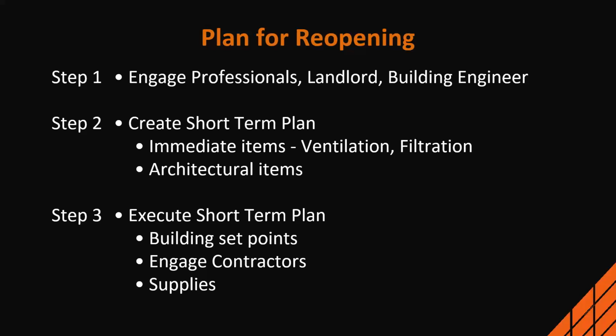Look at the building set point. It's not just a matter of cranking up the outdoor air—how am I going to maintain temperature and humidity, and make sure I get the air to the spaces? If I have VAV boxes, what are the other set points we're going to look at? We need to evaluate our systems. It's not just, hey, I saw this seminar that said use MERV 13s and double your outdoor air—it's not quite that simple. You need to make sure you're not going to create new problems with your systems by doing that.